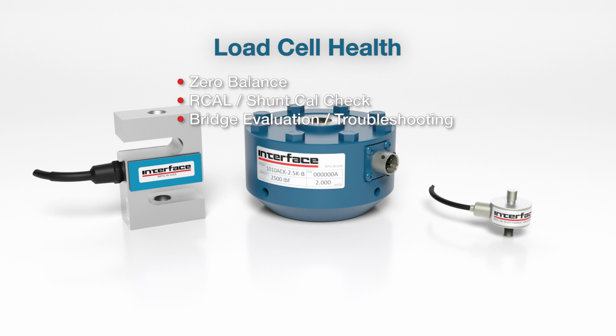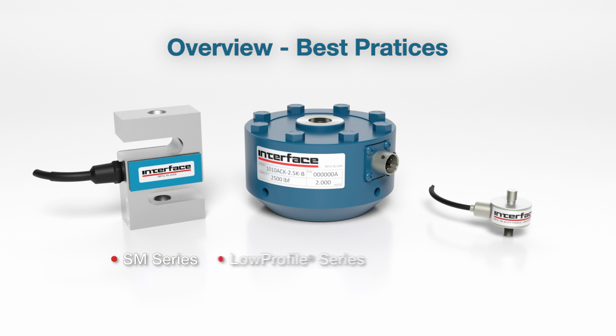Doing a verification of the R-cal or shunt cal is also another good thing you can do. Again, if you see any shift from there, or significant shift I should say, it may be a good idea to get that evaluated. And then if you are suspecting issues with the load cell, please contact us. We do have some more tools you can use to evaluate the bridge of the load cell using a multimeter or other instrumentation options. So we're going to kick it back over to Brian, and we're going to talk about three of our popular load cell options: our 1200 low profile series, the SM series, and the WMC series.